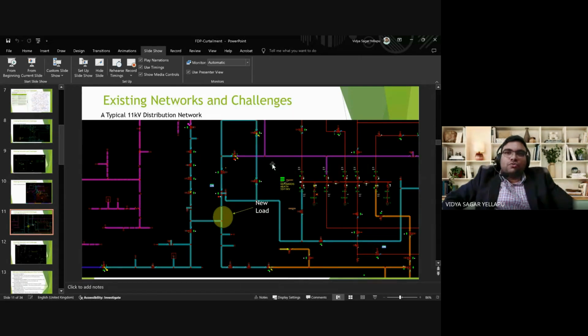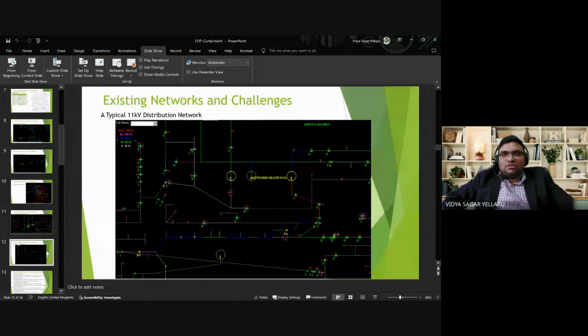But that is not true for the case of a generator. A generator has to adjust to the network it is given. For demand connections, the network can be reinforced. For generation connections, security of supply is not that important, so it has to adjust to the existing network. That is the challenge faced by generation connections, because reinforcement is associated with a lot of public disruption, which is not welcome. This is the overloading scenario experienced by this network for a particular fault condition at this point. This is the same network drawn in some other load flow software.